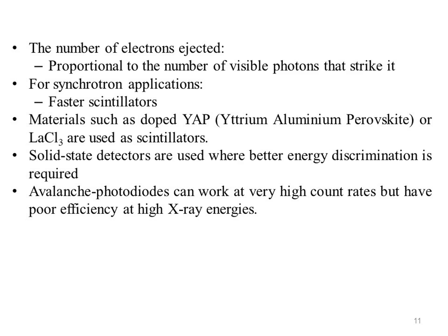Solid-state detectors based on silicon or germanium are used where better energy discrimination is required, and photodiodes can work at very high count rates but have poor efficiency at high X-ray energies because silicon does not absorb such photons strongly.